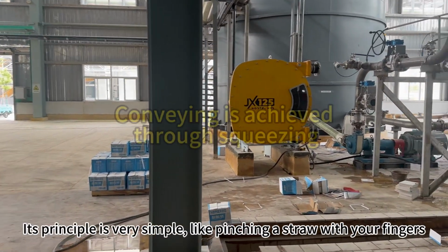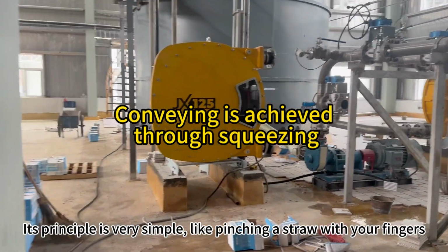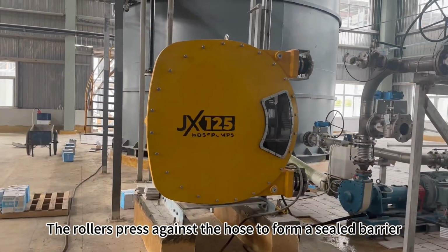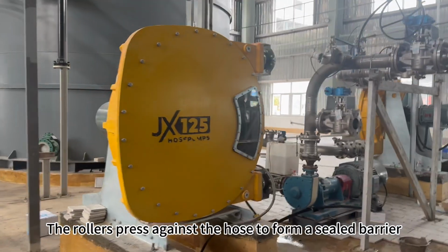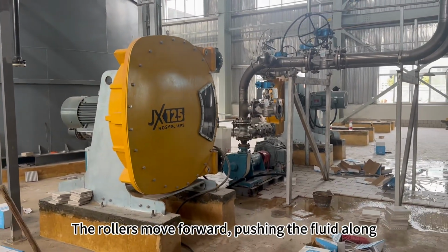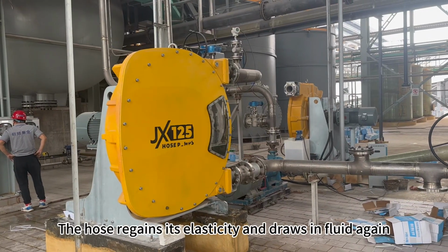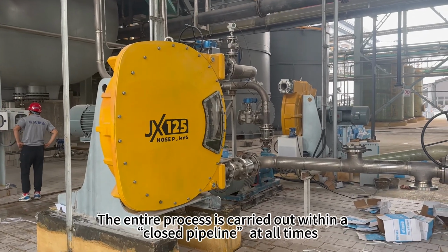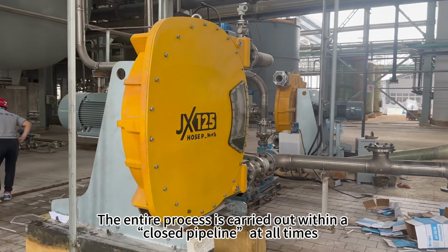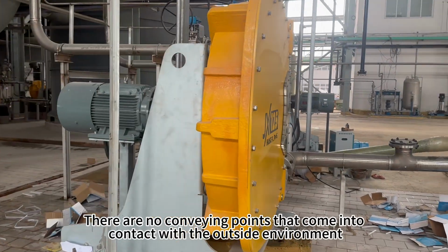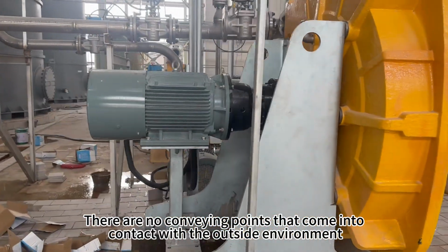path whatsoever. Its principle is very simple, like pinching a straw with your fingers. The rollers press against the hose to form a sealed barrier. The rollers move forward, pushing the fluid along. The hose regains its elasticity and draws in fluid again. The entire process is carried out within a closed pipeline at all times. There are no conveying points that come into contact with the outside environment.